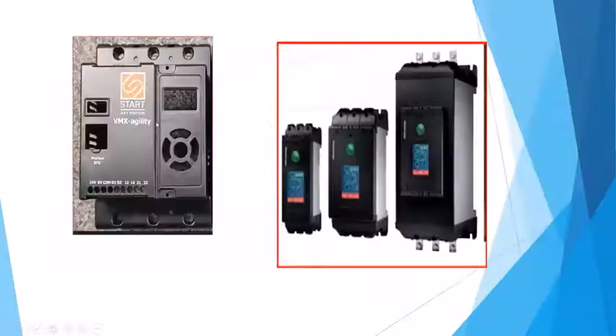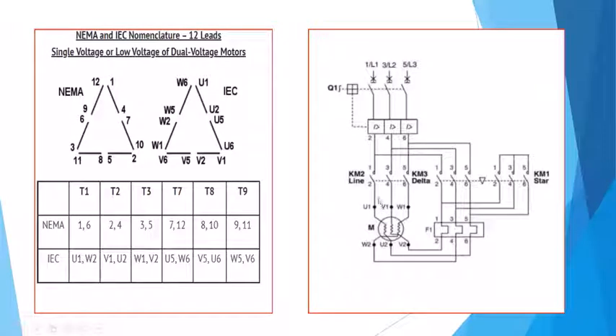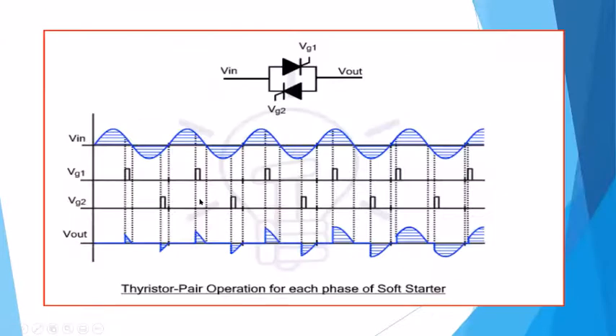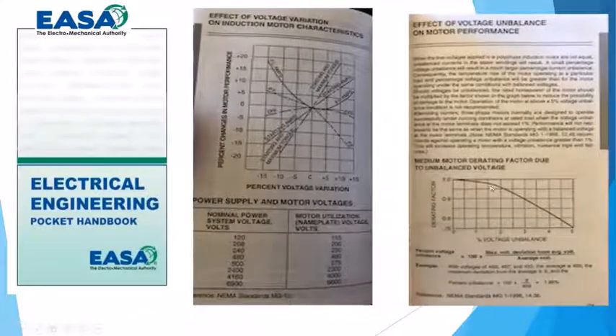So if you've got three waveforms feeding out to the motor here, A, B, C, and you have a voltage drop between here and here, maybe it's like 440 volts, and this is 460 volts, and then between 1 and 3 it's 470 volts. Well, you need to calculate those imbalances and determine where you should be on this curve of derating of the motor. It also has here motor performance: what happens to torque and amperage when you get off of variations of voltage. So if you're at 0, meaning that they're all balanced, or when you start getting off 5, 10%, you can see quickly what happens to the full load amps, the power factor, the starting amps, and torque ability.